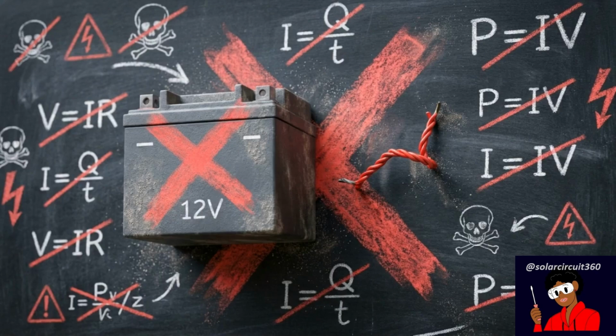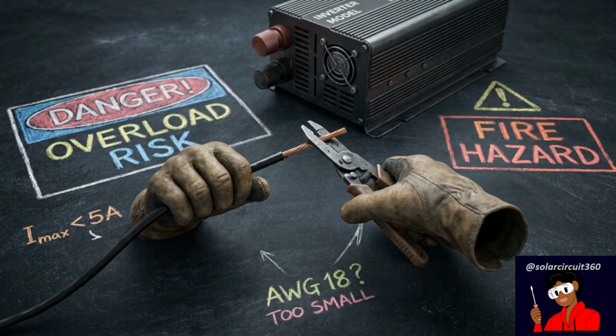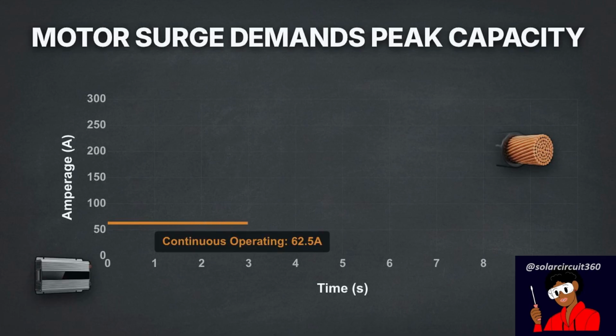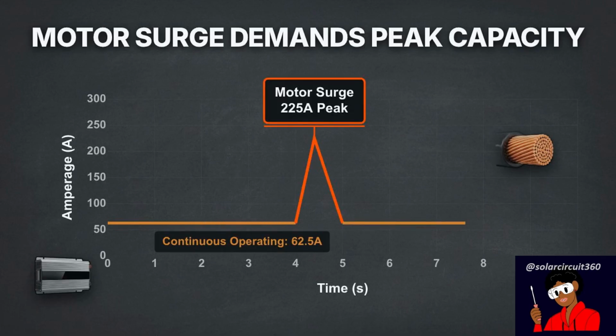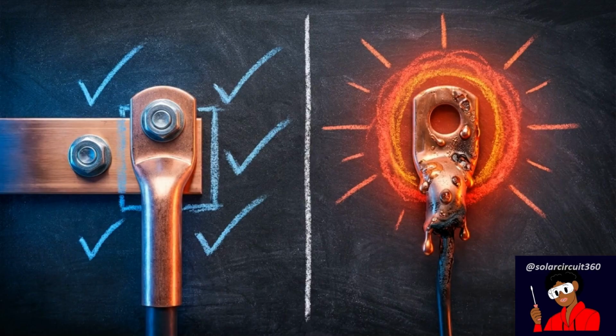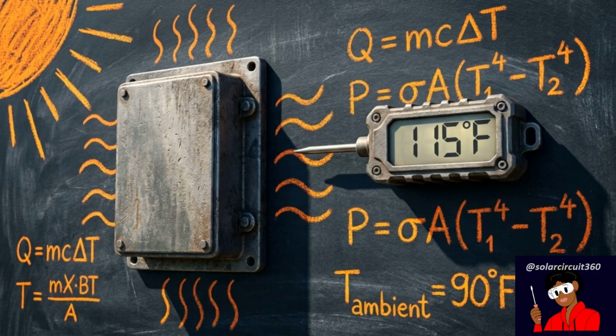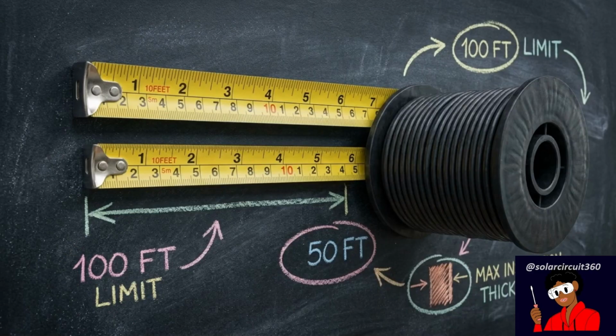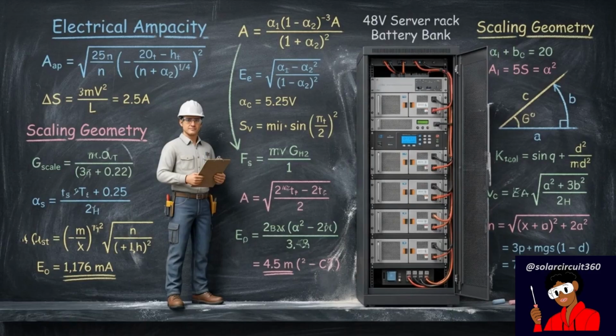There is a common phrase repeated across tutorial channels: 48 volts uses smaller wire. Builders frequently mistake this as permission to use undersized wiring for every component in their setup. The math we just calculated applies to continuous operating wattage. It does not account for the sudden, massive startup surge current required to start heavy motor loads. Even at 48 volts, a heavy inverter surge will instantly melt undersized cables that were only calculated to handle baseline continuous loads. The engineering does not end with voltage. You must still calculate for ambient temperature ratings, precise cable length limits, and the exact insulation thresholds of the wire. Voltage scaling drastically reduces overall copper volume, but it does not replace the requirement for rigorous ampacity engineering.